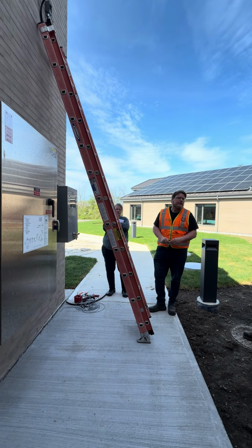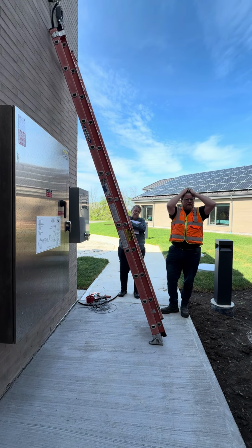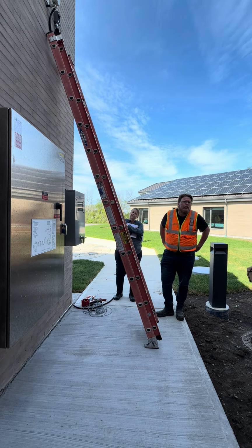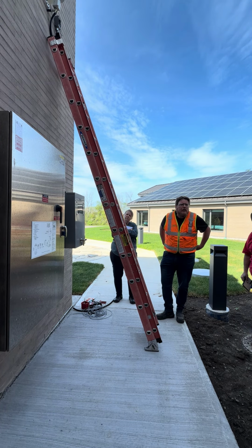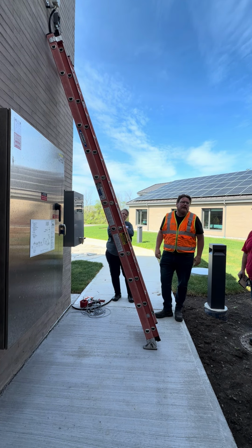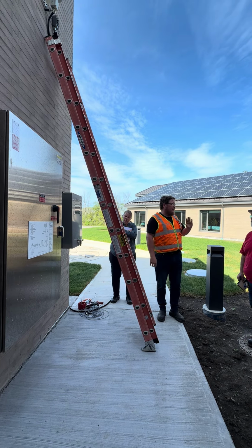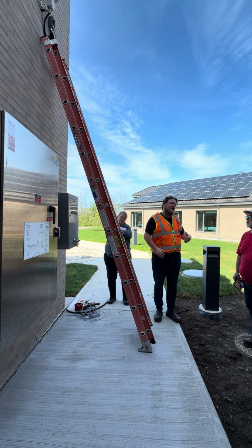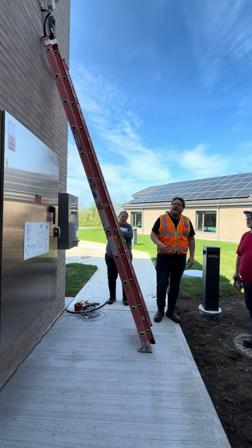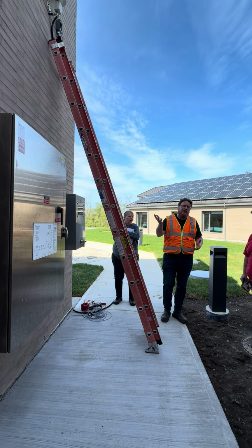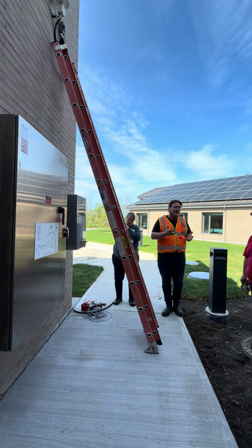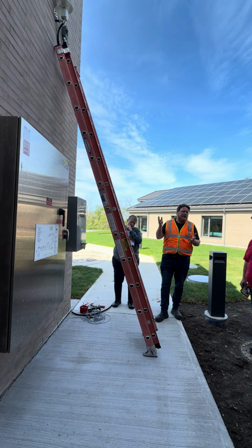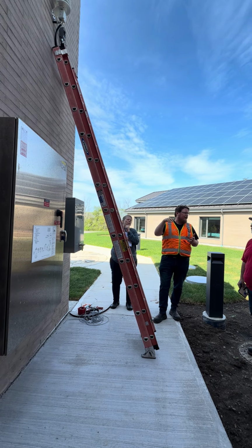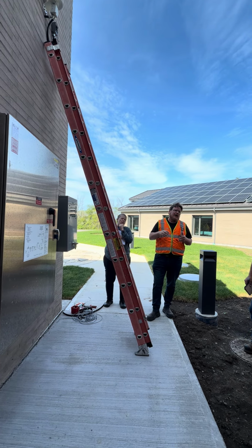So when Hydro remotely disconnects, are they just disconnecting the solar or the whole building? Just the solar. That's a great question. So if they have to disconnect the load, they would do that at the substation, and it would affect everybody on the feeder. Yeah, gotcha. But they can only handle a certain amount of generation on the feeder, and that's basically why. There's some large solar farms south of here. There's some other projects on that same feeder.